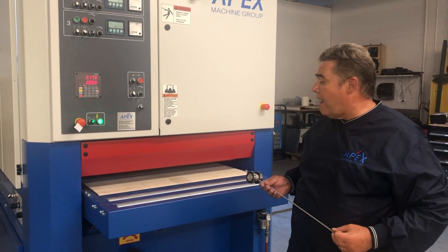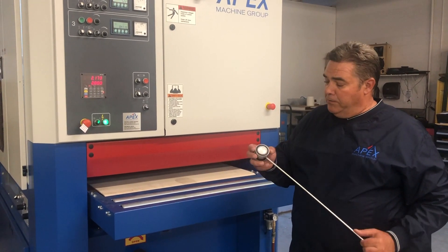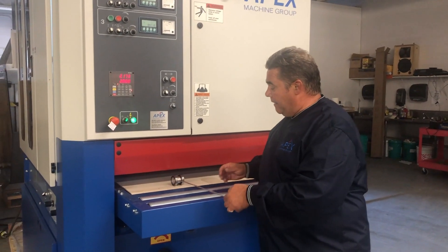In this video, I'm going to show you how to calibrate your bed height to a known value. In this instance, I'm using a tool which is a bearing that is 2.173 inches in diameter. So I'm going to calibrate the bed to that number.